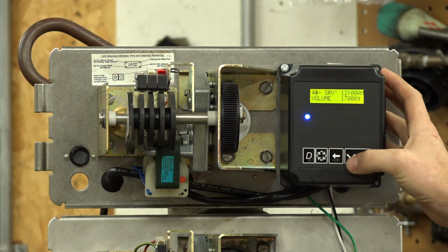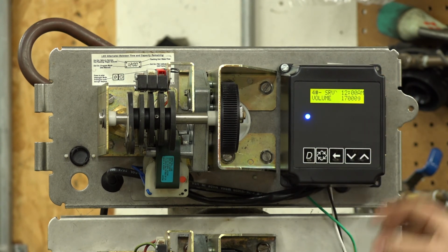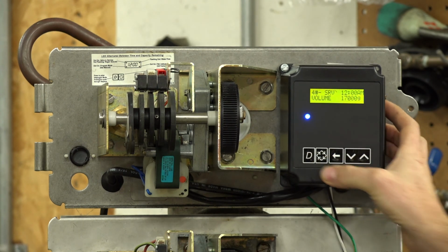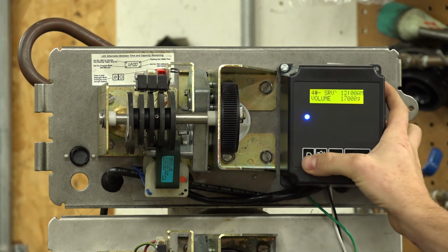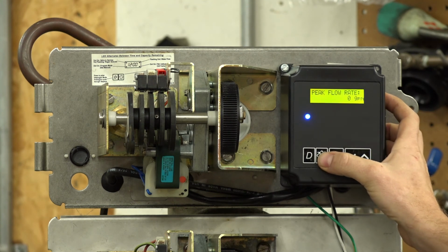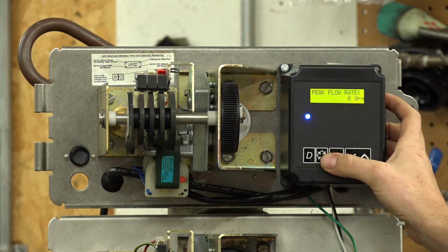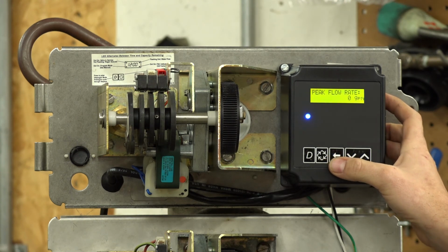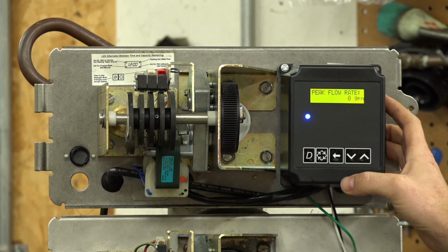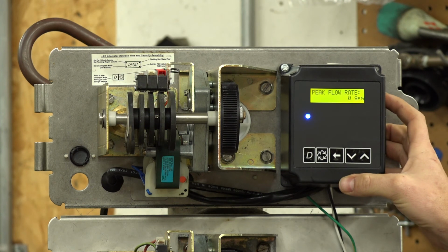The other thing you do have with these valves is a D button, which is your diagnostics button. If you press that, it shows you current flow rate. If you press it again, it goes back to your main screen. Now if you press it and it says current flow rate, and then you hit your regen button, that takes you through the other items. I consider those to be your preventative maintenance type checks, the things that your maintenance supervisors or managers or personnel are going to be going through and recording on a regular basis, because it's the pertinent information that this valve is recording and computing for you.